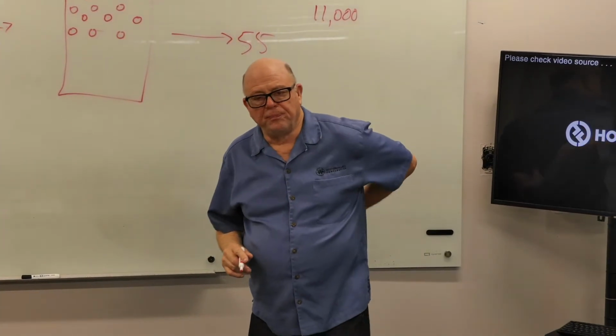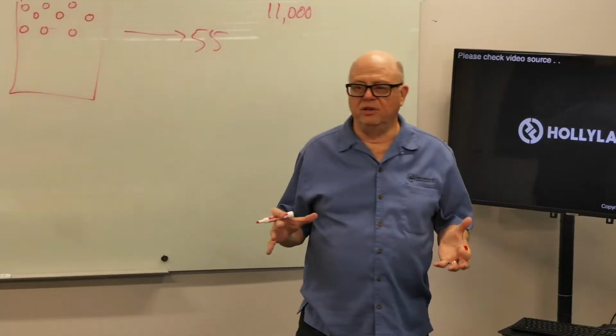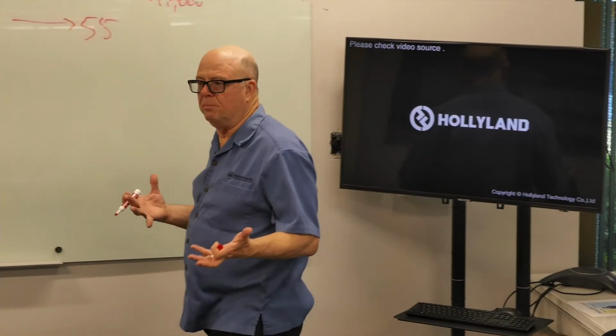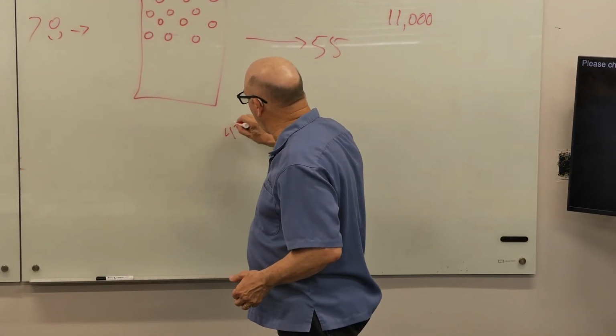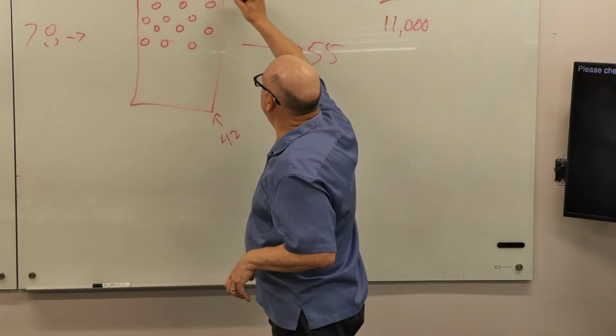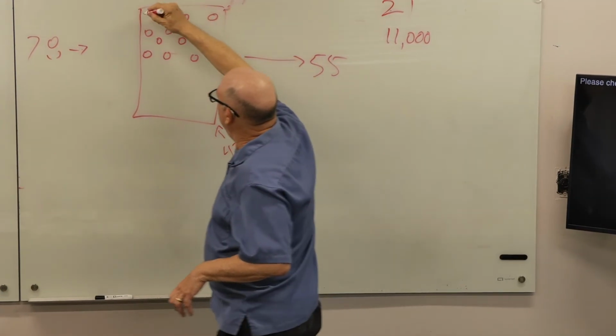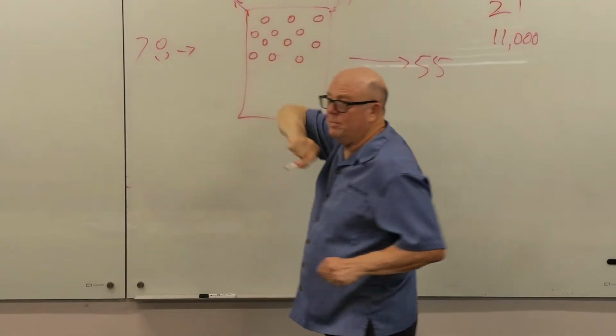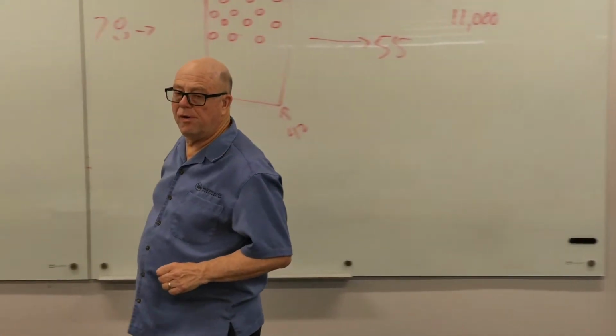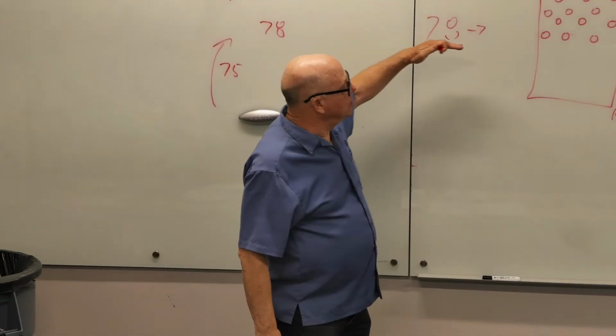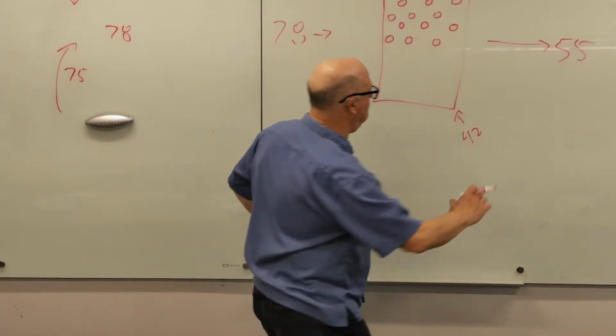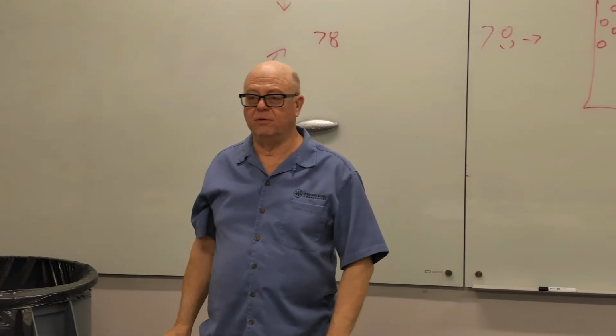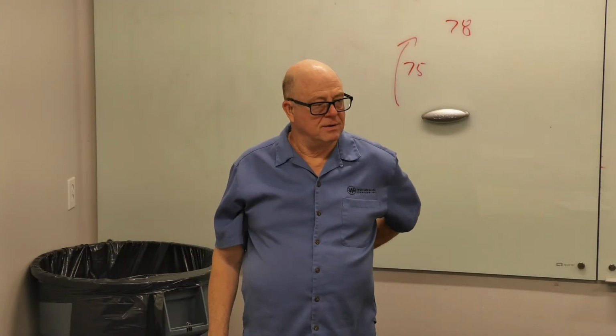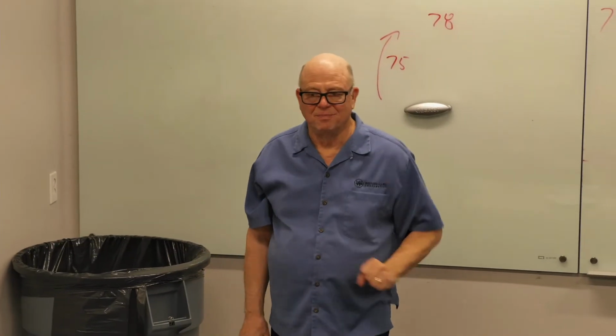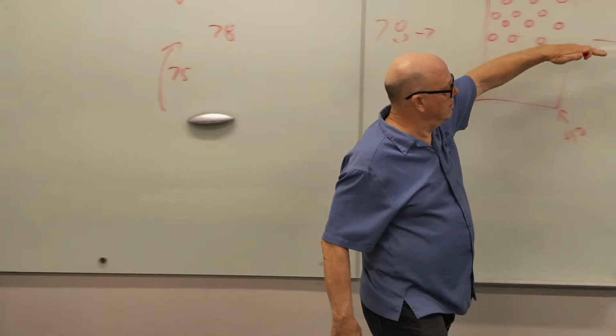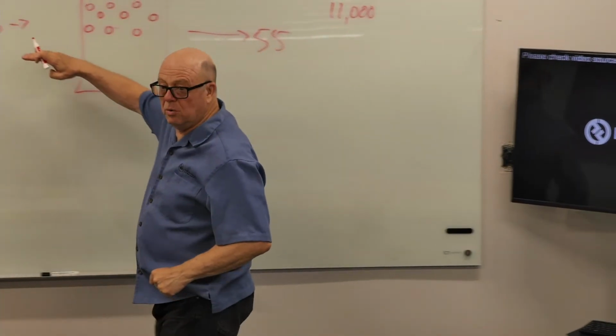Okay. Now, let's say that I'm actually designing this thing as though energy counted, and that value is important to me. And let's say I was putting 42-degree water in, and I'm taking a 16-degree rise, so I've got 58-degree air or water coming out. What's it called when the thing you're heating is going this way and the force you're using to cool it is going the opposite direction? Heat exchanger. Yeah, it's a heat exchanger. It's counterflow, right? Because you've got what you're cooling going this way, and what you're using to cool it with is going back opposite direction.